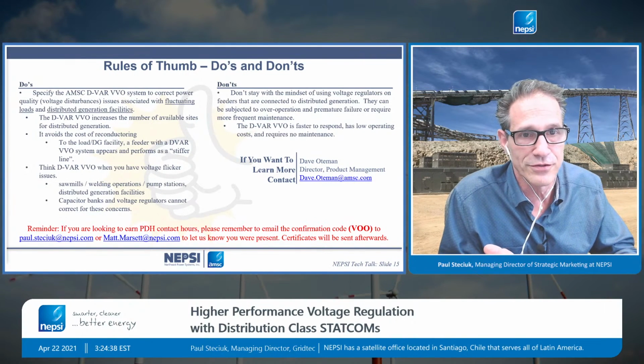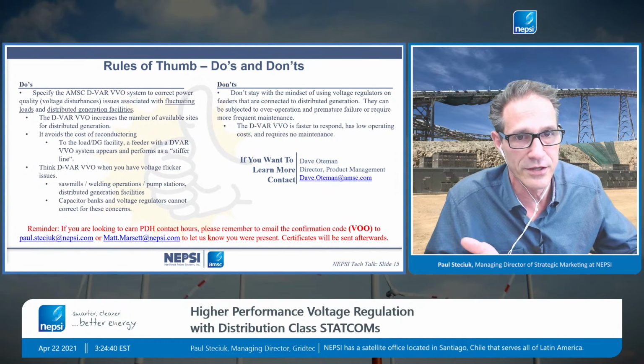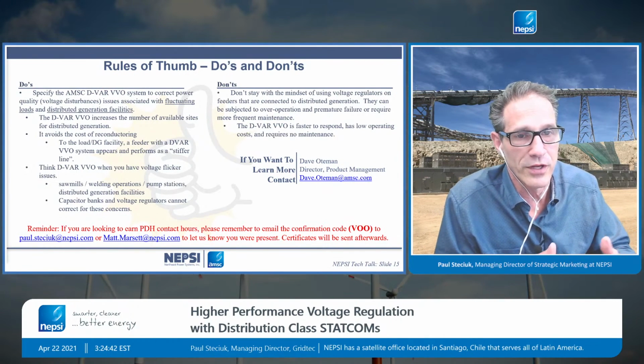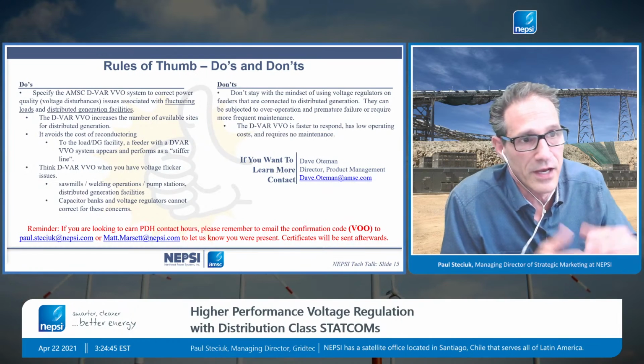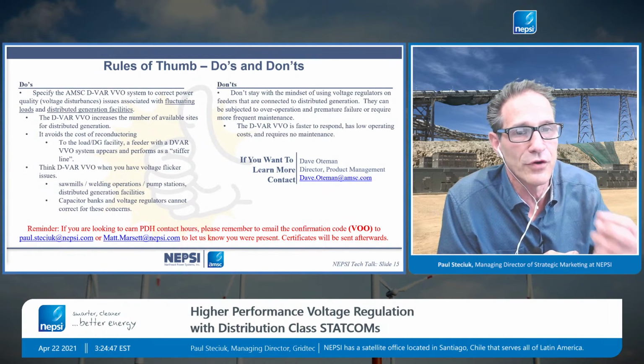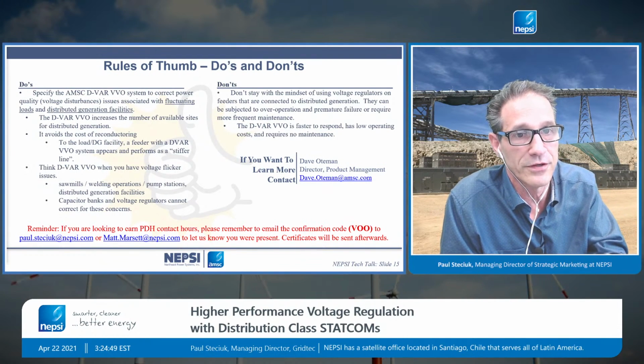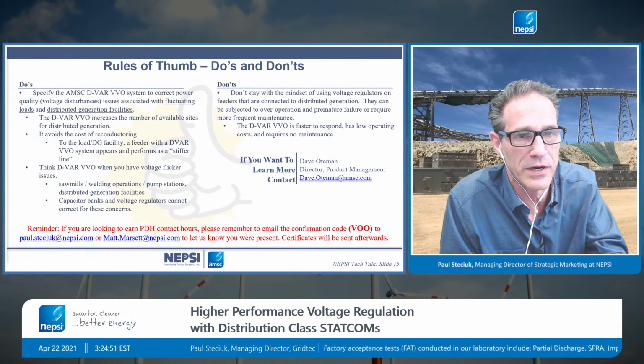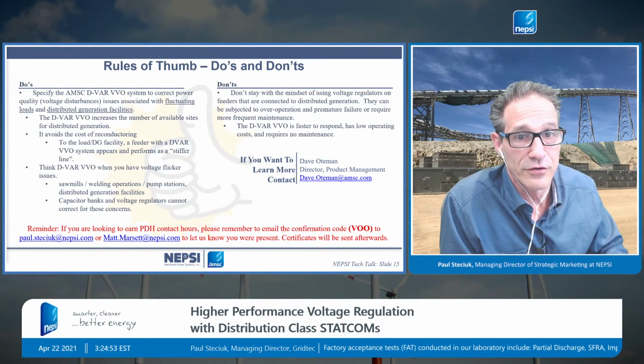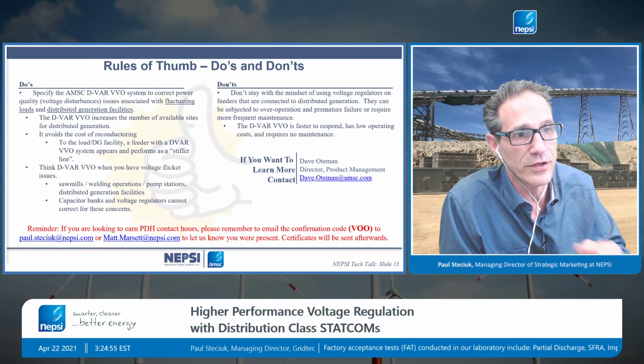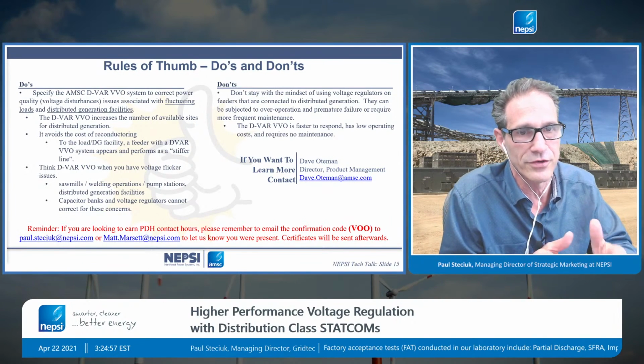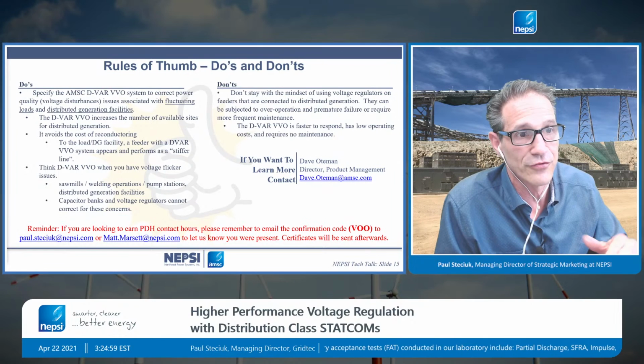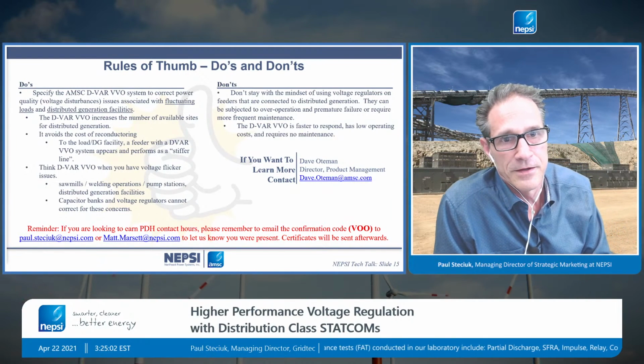Much of our distribution systems are weak, the distribution lines are long, and 13.8 kV isn't that high a voltage, so it doesn't take much current or injection, whether real or reactive power, to push that voltage around. The VVO can help stabilize the system as we increase distributed generation penetration into our networks.